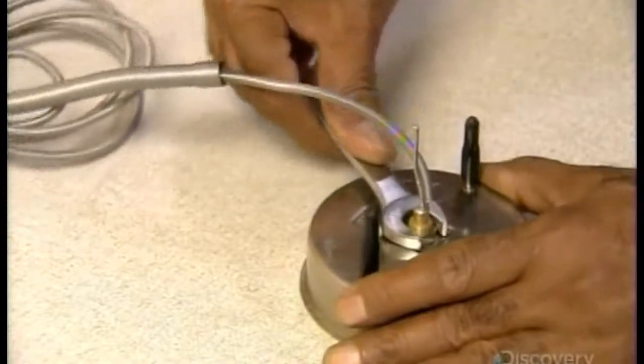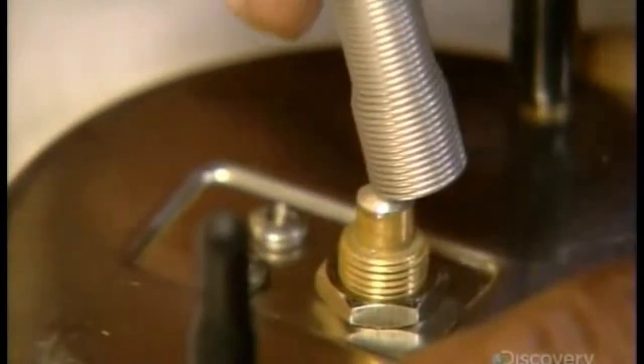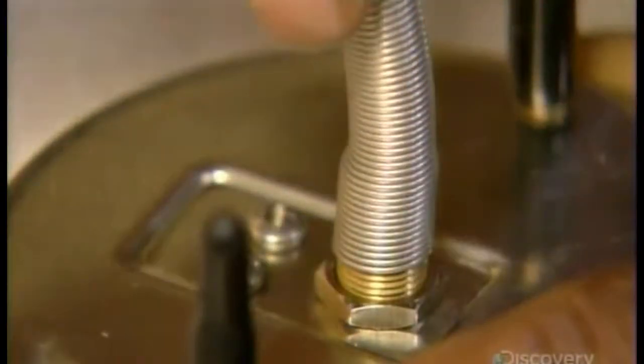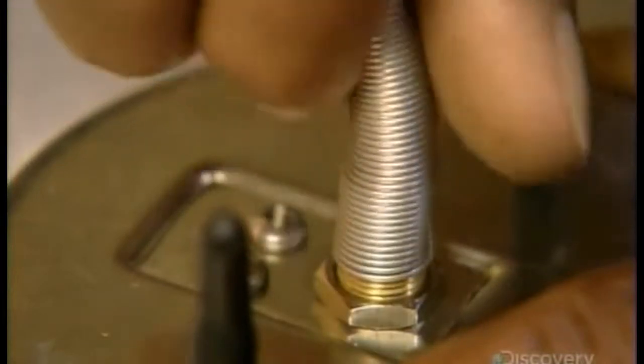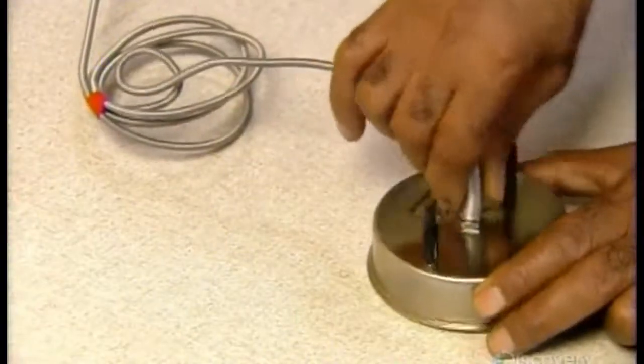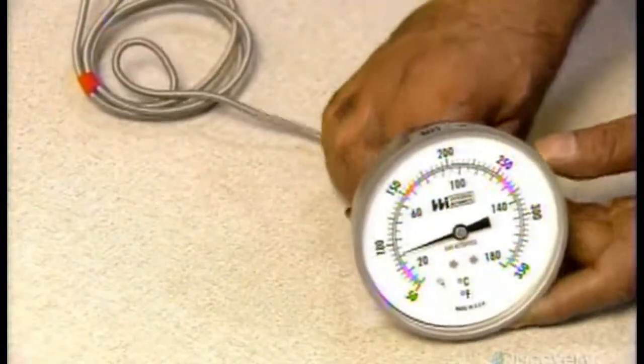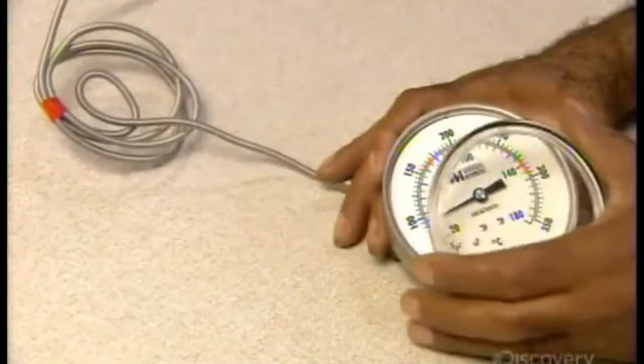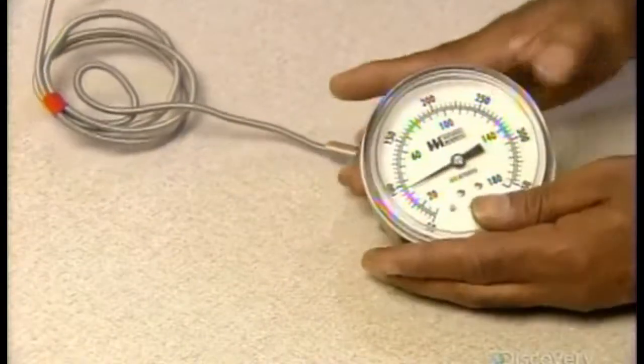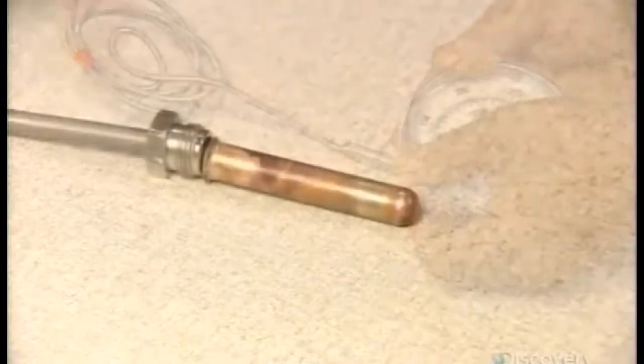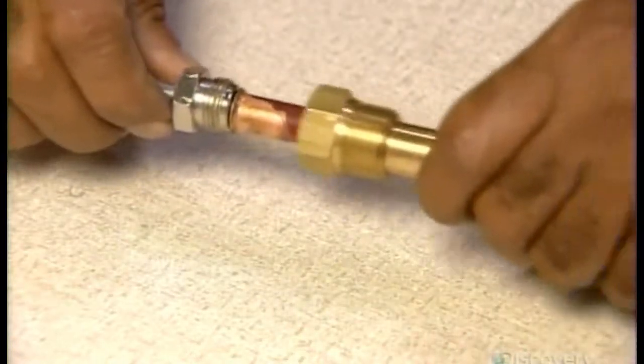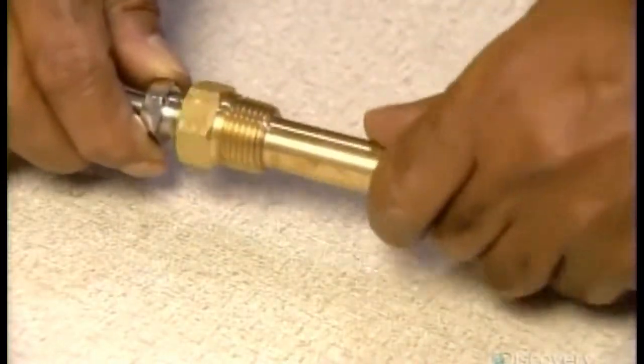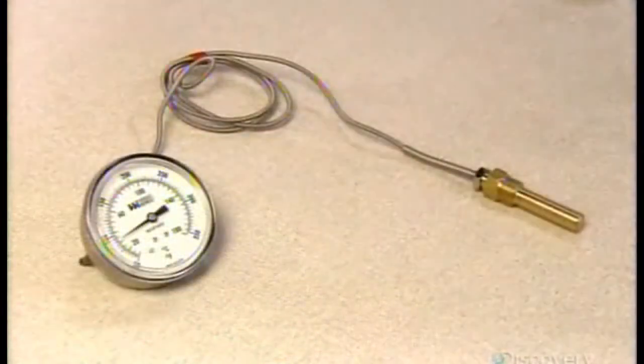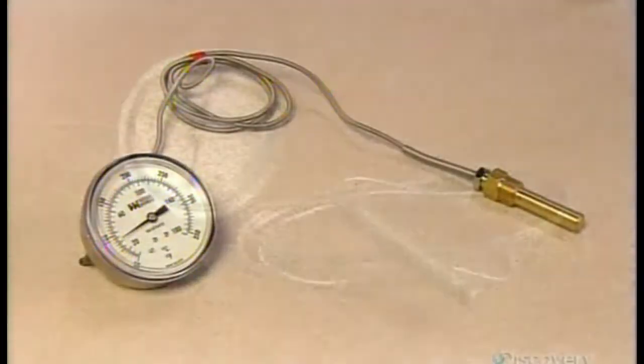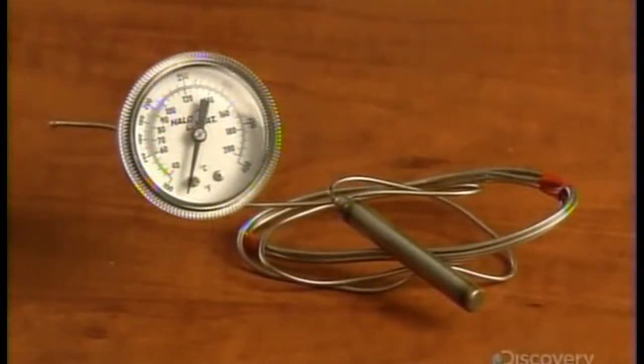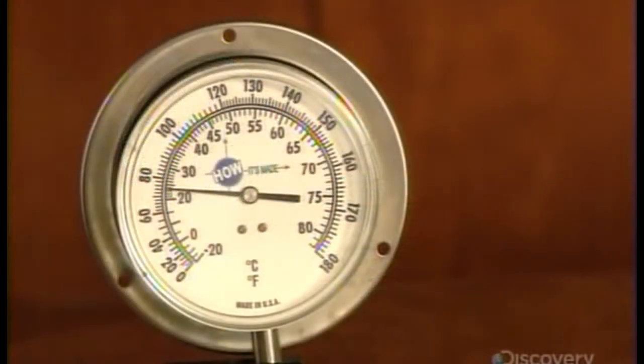And if it's on the mark, he encloses the inner workings in the stainless steel case. He protects the joint with a special metal spring and snaps a clear window to the case. A gasket between them ensures a dust-proof seal. He screws a part called a well to the sensing bulb connector. The well will protect it in high-pressure situations. This dial thermometer is now ready for the ups and downs of temperature gauging.